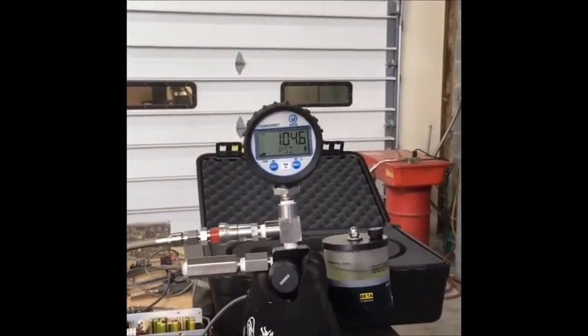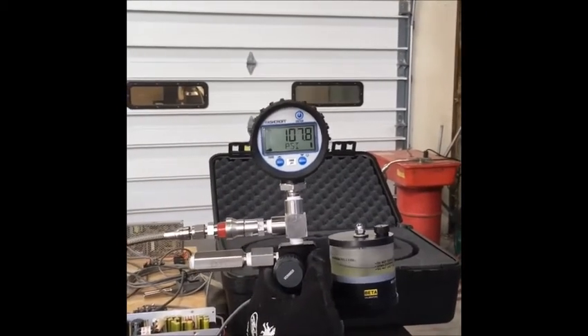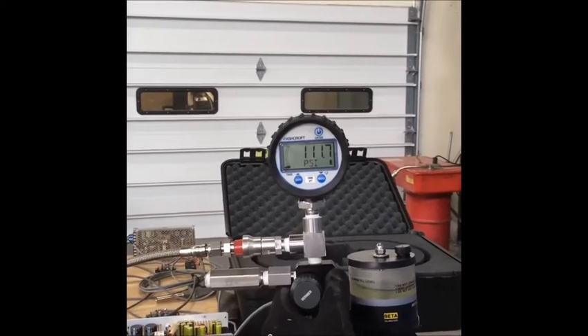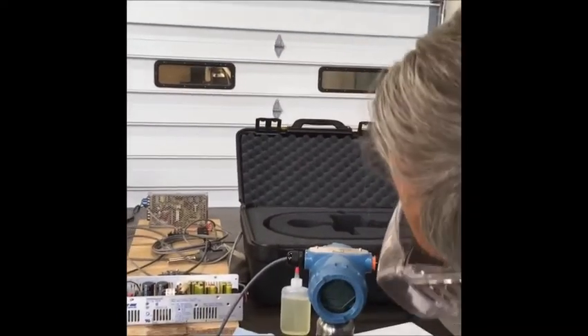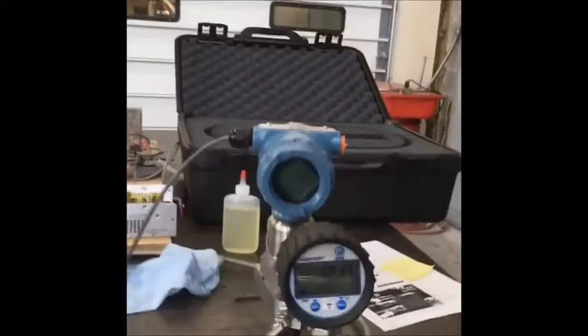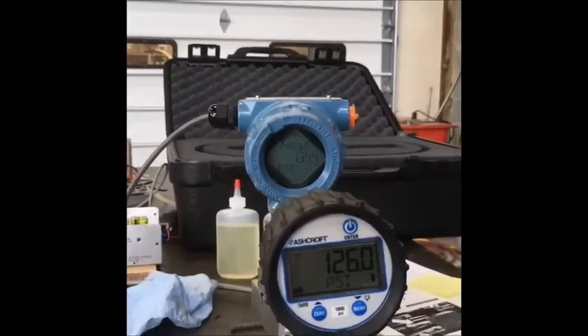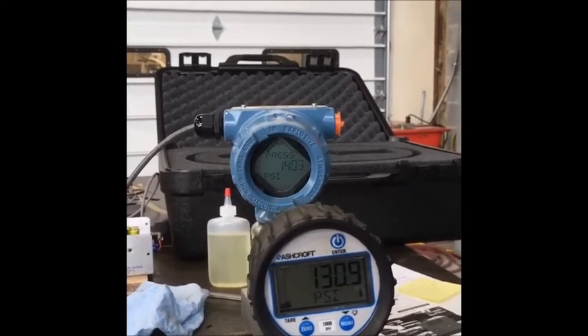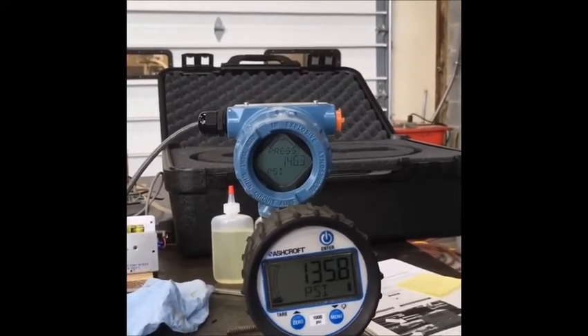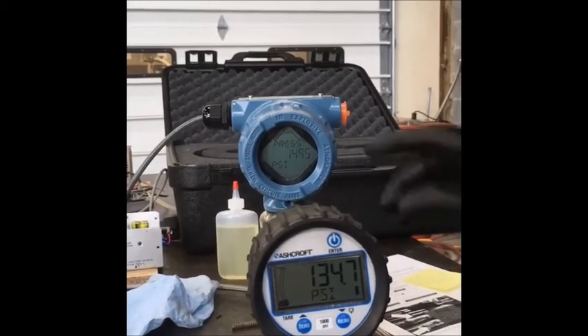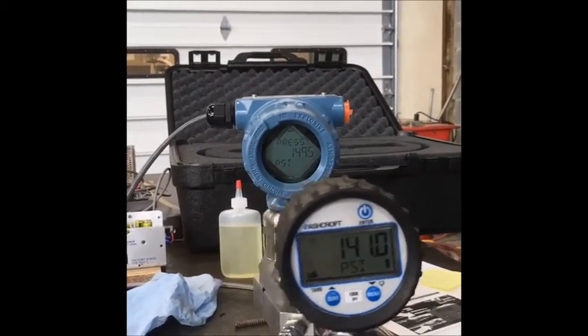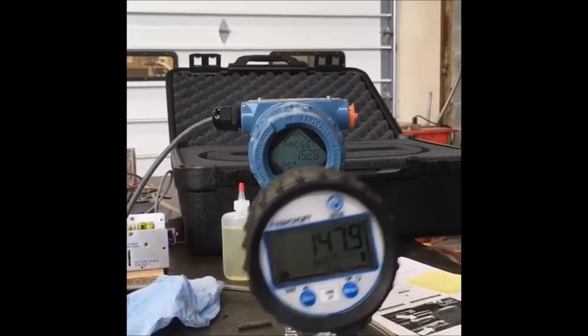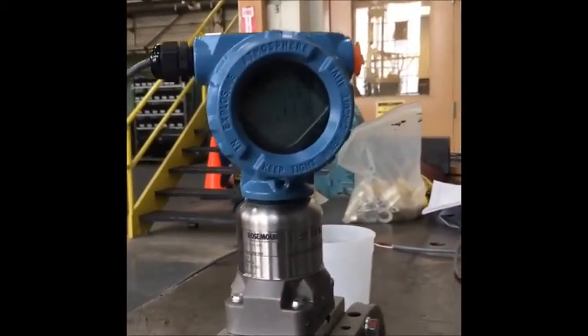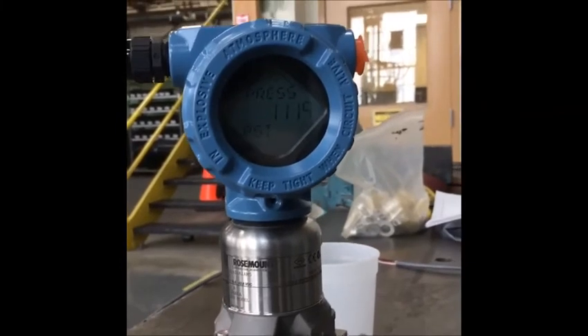101. So now again, this device is set gauge, and my transducer is in absolute, but at some point here you'll see that the pump will start to take over right about there. Now I'm starting to raise the pressure on the high pressure cutout, and you can see as this device is pumping oil pressure into the system, I'm starting to raise the pressure at my high pressure cutout. Okay, so now the rest of the way we're just raising the pressure on the hydraulic fluid. That particular one will not go up. That's the discharge pressure, so it's not going to feed backwards over there.